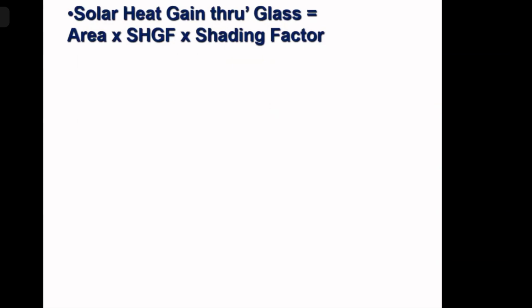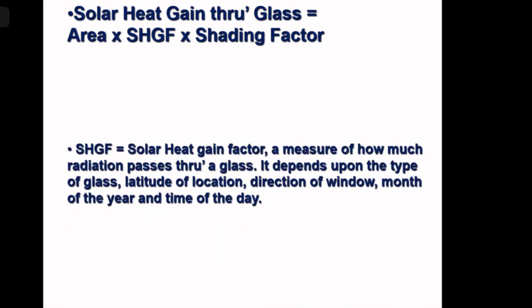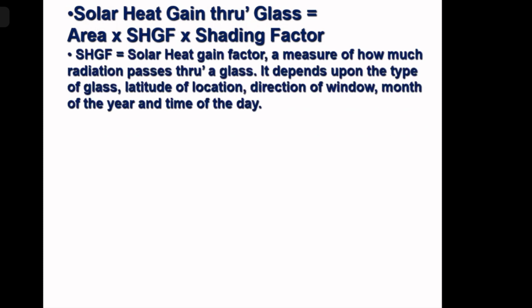Now, direct solar heat gain through glass, which is direct solar radiation coming in, is area into solar heat gain factor into shading factor. If you are using curtain, then each curtain has got a shading factor. So area into solar heat gain factor into curtain. Solar heat gain factor is a measure of how much heat the glass allows. It depends upon the type of glass, latitude and location, direction of window, north, south, east, west, and year and time of the day.